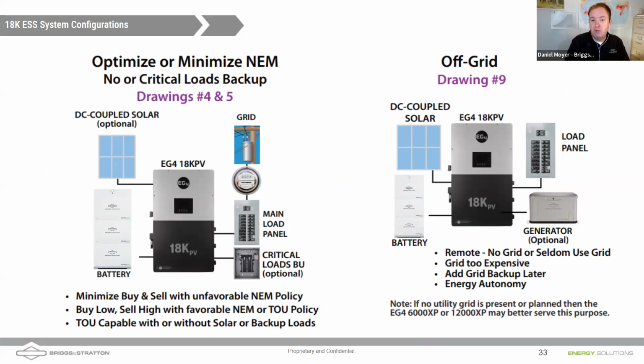You may be able to move all of those loads from the load center down to the critical loads backed up panel. There are a lot of situations where they may already be moved. A lot of people have either underground or overhead service coming into a meter socket to a disconnect, and then elsewhere in the house is that loads panel that's already been populated with the breakers. So we absolutely don't need to relocate anything. We can go ahead and just back up the entire system.